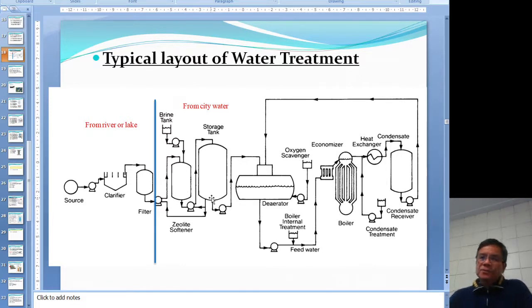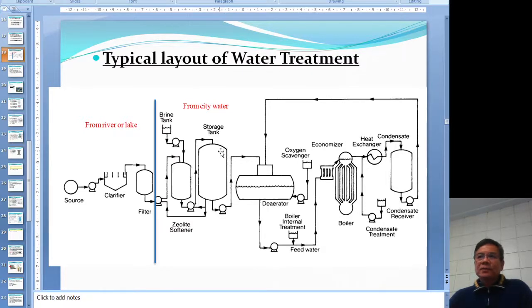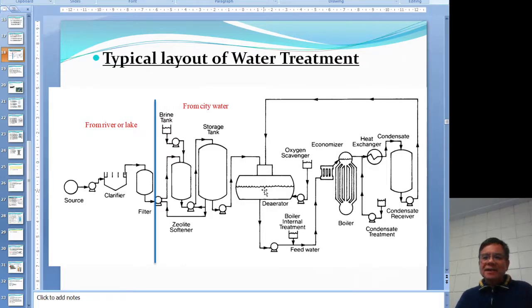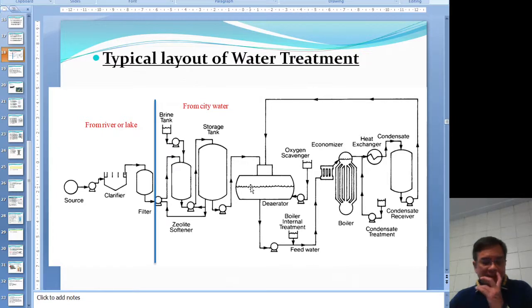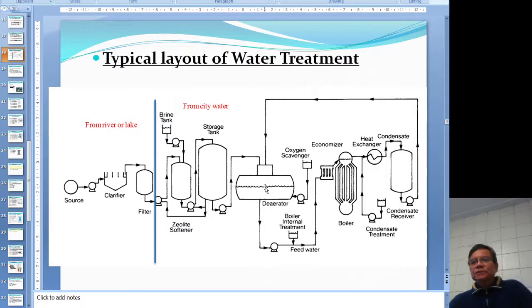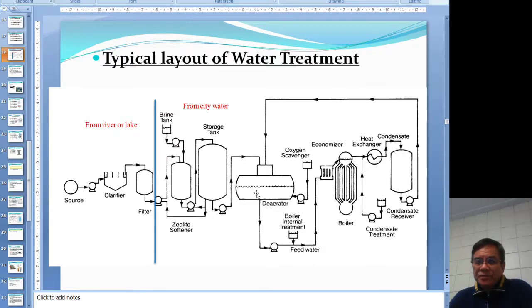After the storage tank, you use a pump to pump it to the de-aerator, or just use the city water pressure - lots of times city water pressure is good enough to push into the de-aerator. The de-aerator has two functions: the first, as the name indicates, is to take the air away. The second is to act as a storage tank. When the de-aerator is about 50% full, the top half of the dome is reserved for steam to take the air away. Sometimes you also add chemicals in the de-aerator.